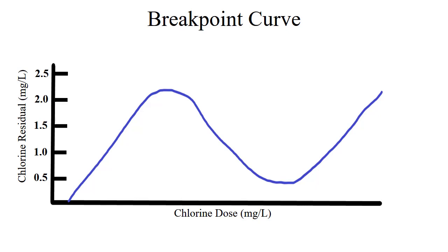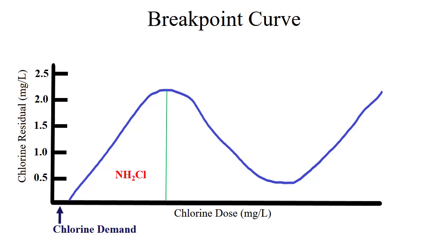When chlorine is added to the water, it reacts with compounds that have an oxidant demand. This is called a chlorine demand. For example, iron, manganese, and natural organic matter react with chlorine but do not form a chlorine residual. Consequently, there is a gap on the x-axis before the curve starts to develop. This gap will vary depending on water quality. Once the chlorine demand is met, the chlorine can react with ammonia to create monochloramine. As more chlorine is added, the monochloramine concentration increases until it reaches the maximum at this peak. At this point, the chlorine-to-ammonia-as-nitrogen ratio is 5 to 1.